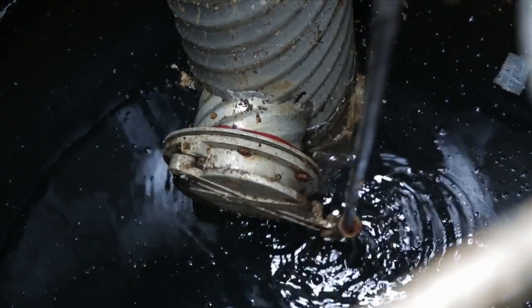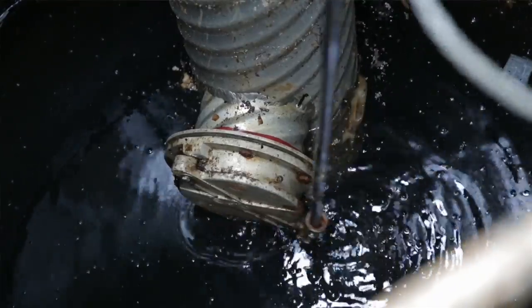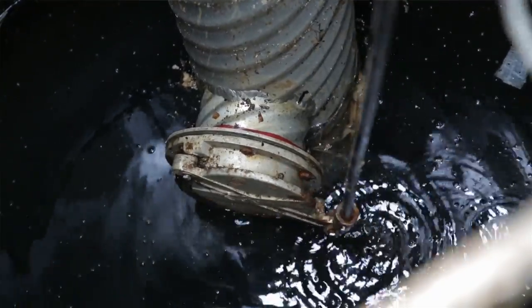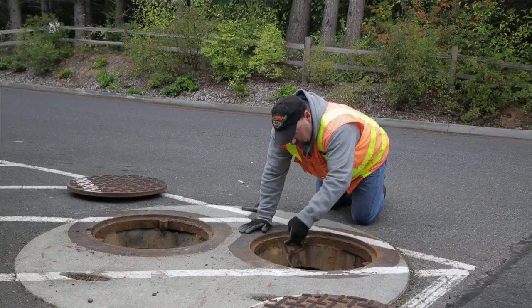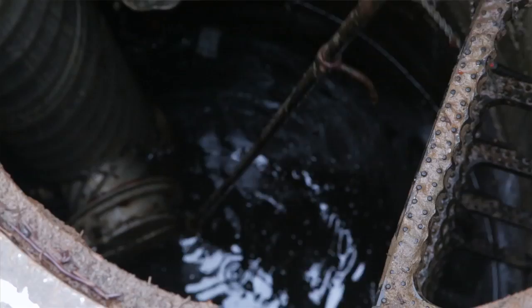So as you're inspecting the shear gate, you want to be sure to exercise it. And simply that means open and close it 3 or 4 times. You're looking for a full range of motion. By doing that, you're flushing water down the exit pipe. You're making sure it's not getting stuck in place with rust or something along those lines.